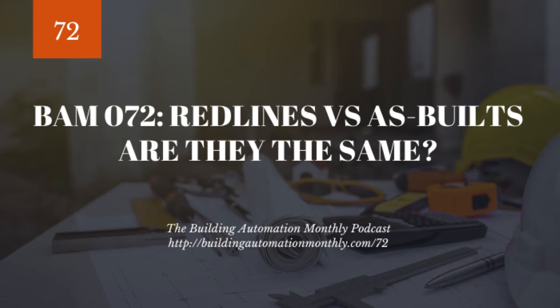So really, what are the differences between red lines and as-builts? Red lines can happen throughout the project. You can have multiple red lines. Okay, so you can redline, and then you can submit your red lines up the chain through a request for information or a request for clarification, and then be told not to include your red lines. So you never want to base your service on red lines. Red lines are not necessarily as-built conditions.